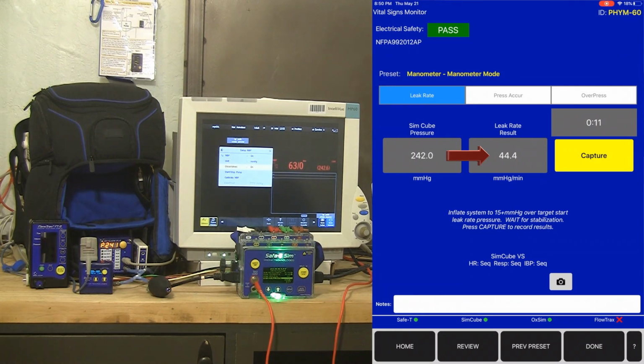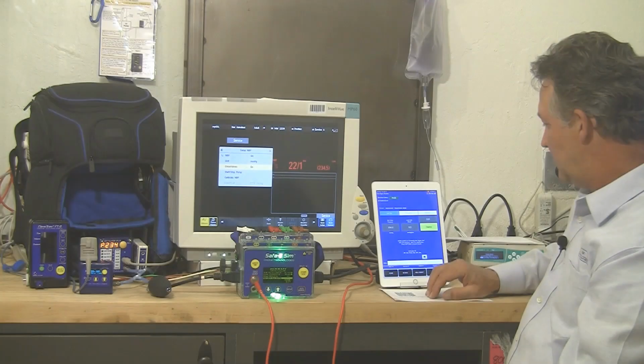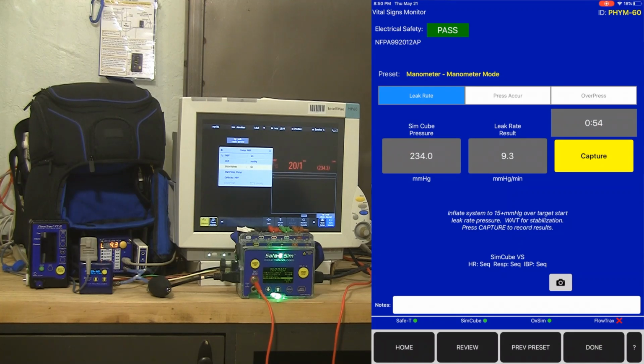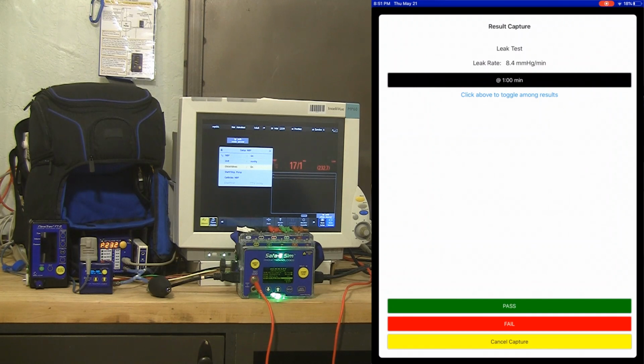So we've got now a leak rate result in this box. We've got the sim cube pressure in that box, and we've got a timer that lets us see where the time elapsed is in the leak rate testing. So we're at about 53 seconds now, so I'm going to go ahead and hit capture. You don't have to hit capture right at 1 minute. If it goes over 1 minute, you can hit capture and choose 30 seconds or 1 minute or 1.5 minutes, for example. We've gone over 1 minute. I'm going to hit capture.